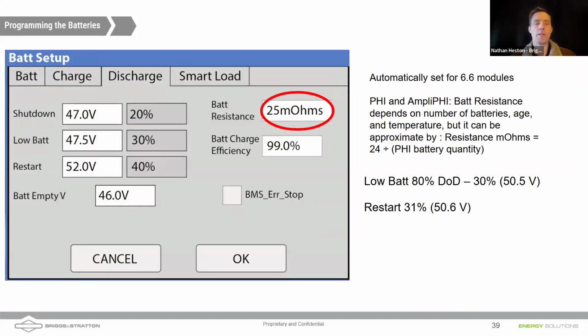Here we're looking at the values which the Sol-Ark will respond on the discharge side. So let's suppose your Sol-Ark is running off of batteries. You've got no solar coming in. You don't have the generator starting up, etc. We've just got a regular discharge going here. And when the battery gets to 30%, that's when you start to get a low battery signal. So the inverter will start beeping at you. Your battery's getting low. When we hit 20%, as we've got set on the screen, and these are changeable, what happens, Daniel? The voltage starts to drop, not relative to the state of charge.